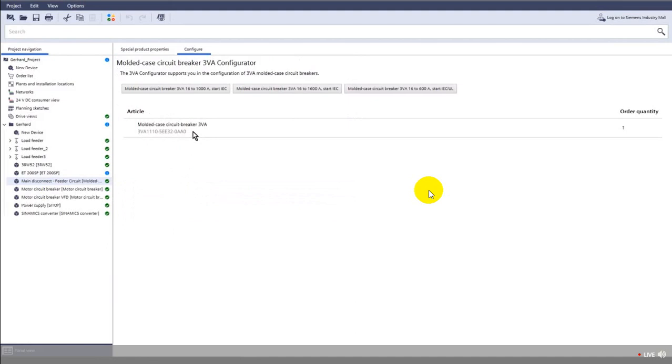I see that you also took into account the rotary switch. Great. We can work with this. But you were mentioning some changes. What happened? Well, actually 3 major changes. One motor needs to be sized differently concerning the power. Okay. At one motor branch, we need to significantly change the conductor lengths, the cable lengths to the motor, and you told me that this really matters.